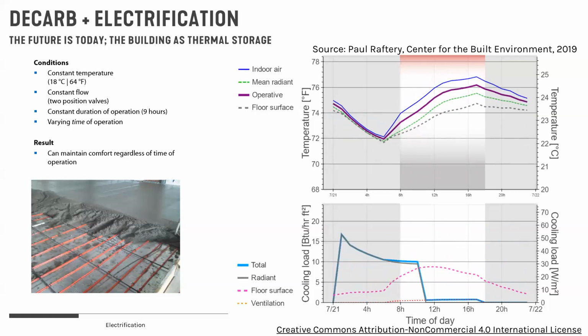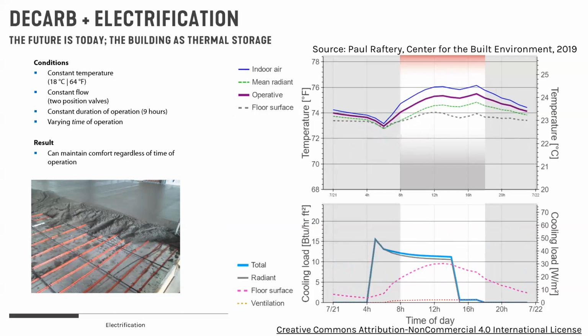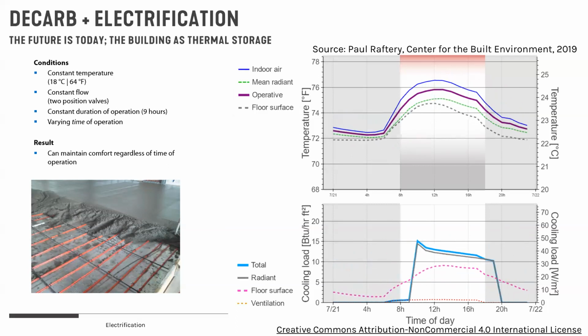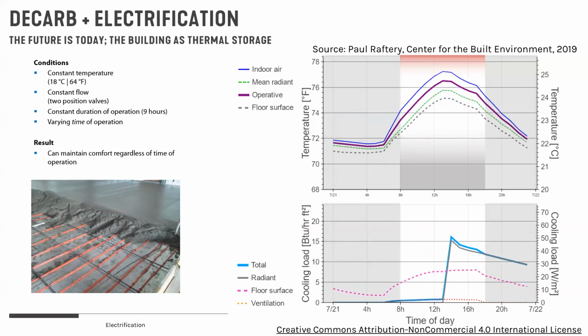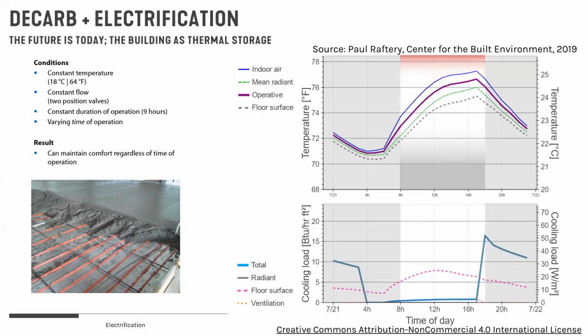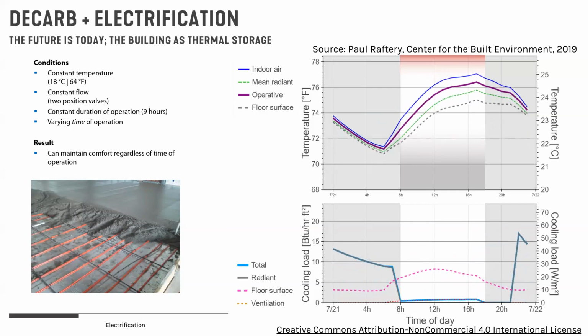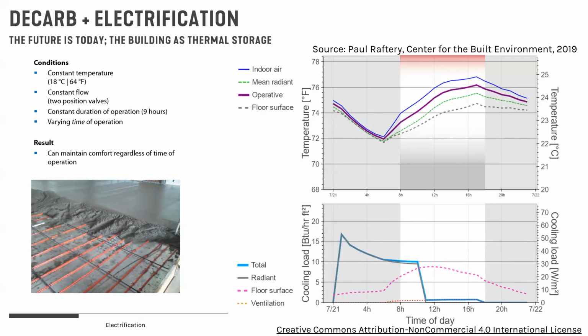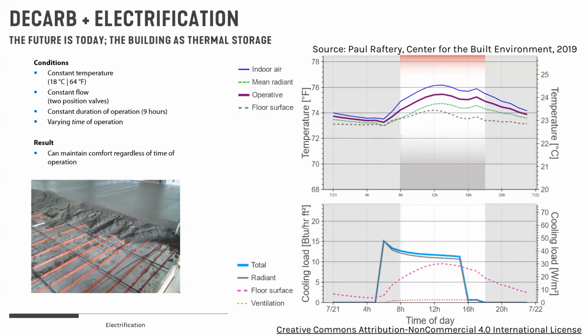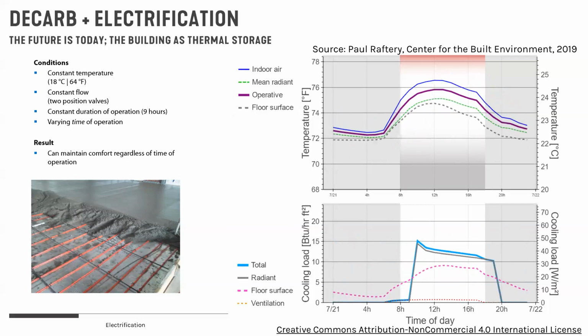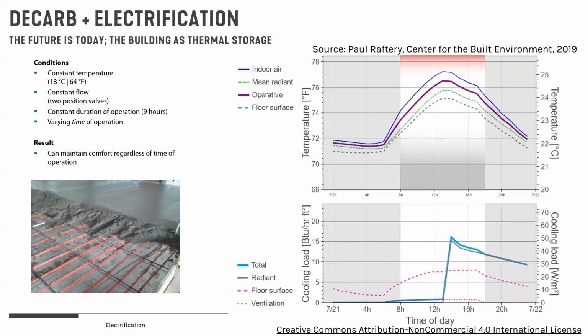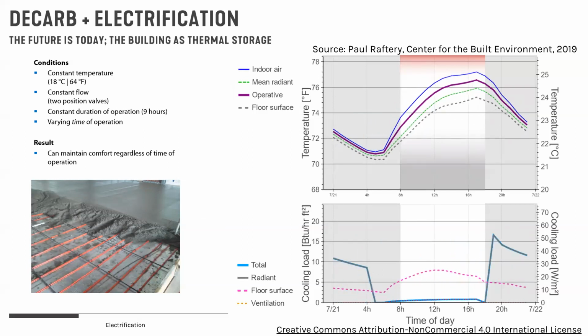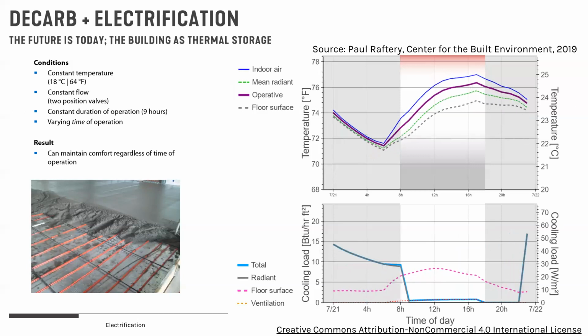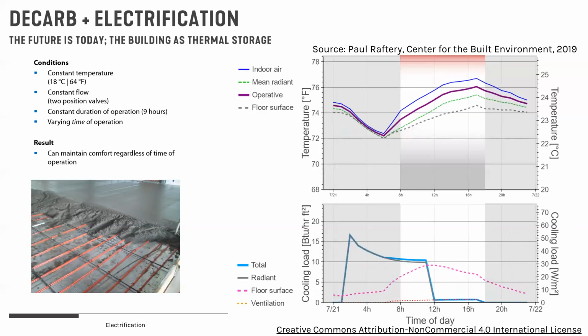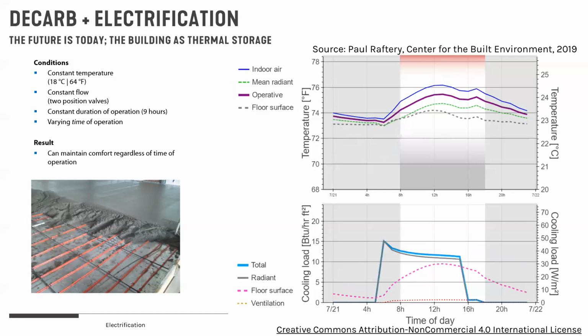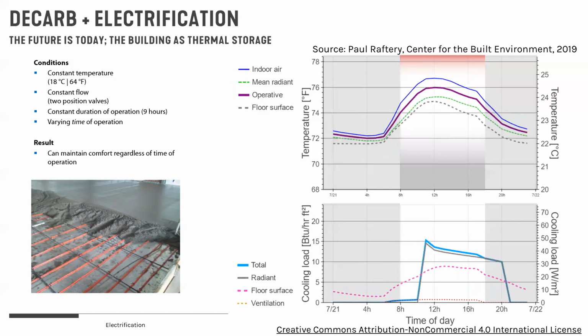to still provide comfort. The research shows that if we just pick, say, nine hours, and provide chilled water to that slab for nine hours, we can move when we do it almost any time throughout the day and still maintain comfort in the space, because the inherent lag in the slab, the thermal storage of that slab, gives us a lot of flexibility.